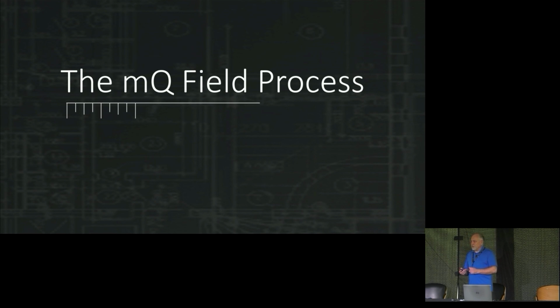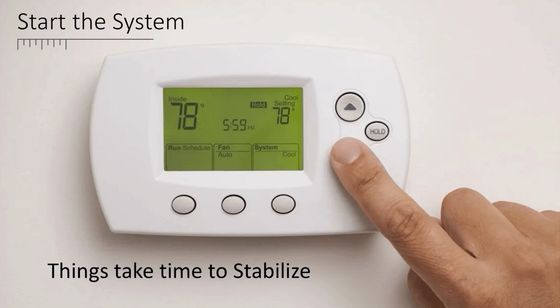Yet how many guys, the first thing they want to do is go gauge up on a system and try and fix the problem with refrigerant? How many of you guys when you're young in your career added 4 or 5 pounds to a system, or me, I added 30 pounds to a system before you figured out the blower wasn't running, right? I mean, you go out there and you go, oh, frozen up, low on gas, adding gas to the machine, right? All of us have done that, but that's the last thing we should be doing. We should be going through and doing this visual inspection first, and that's where you're going to get the most out of the software.